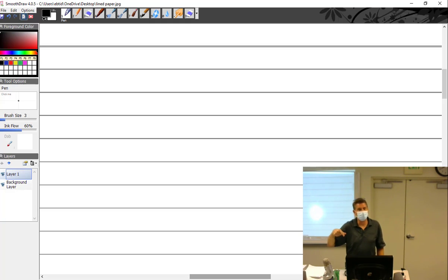Now, we could actually just go back and ignore this whole voltage drop thing. I could never mention it, not even worry about it. Just follow the chart: you've got X number of amps, X number of feet, what size wire? Boom, that's the size wire. Then it's like, well, why is it that size of wire? Two things: one, it's the current carrying capacity, and two, it ensures you don't have a voltage drop that's too much. Hopefully that makes sense.